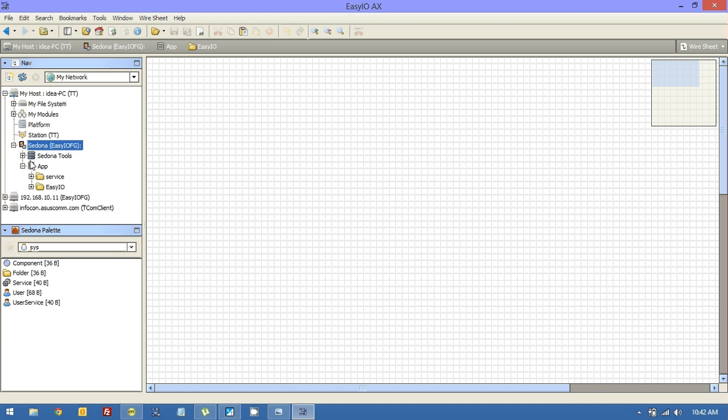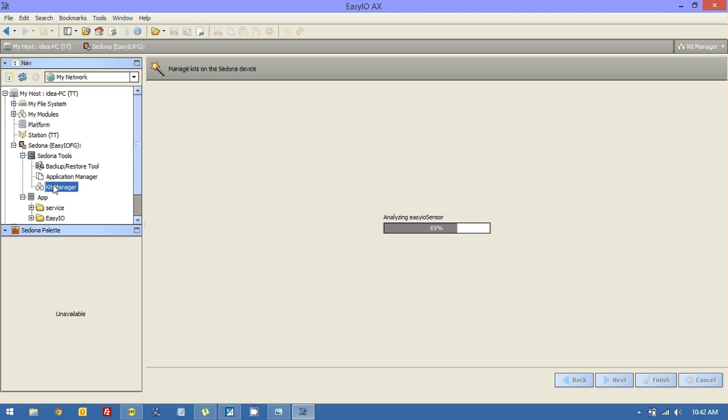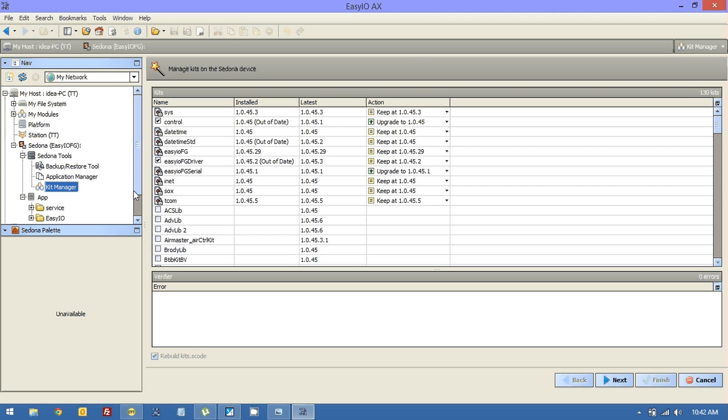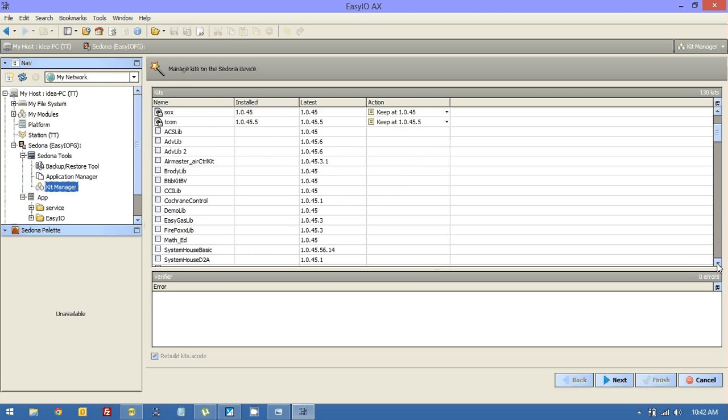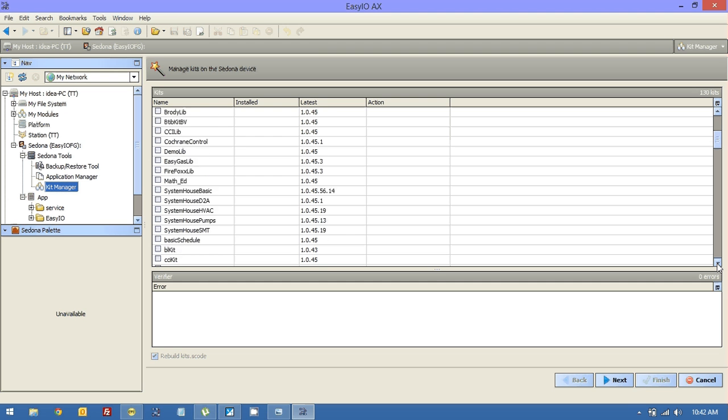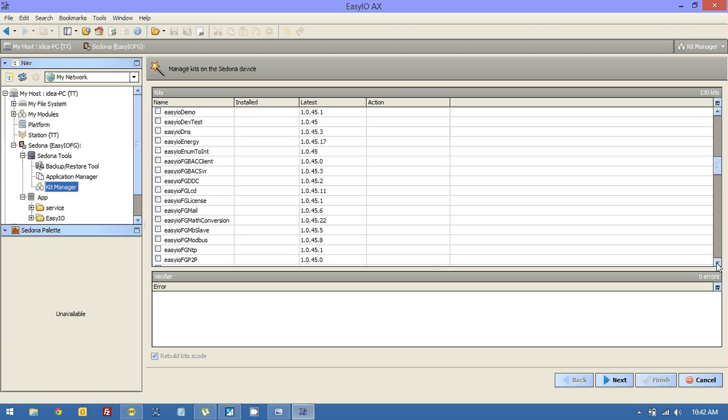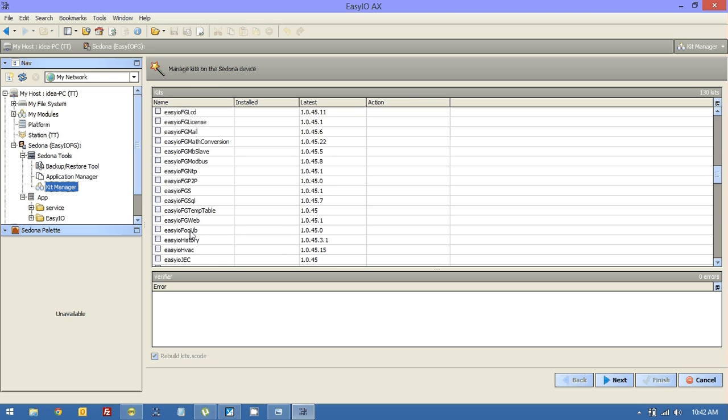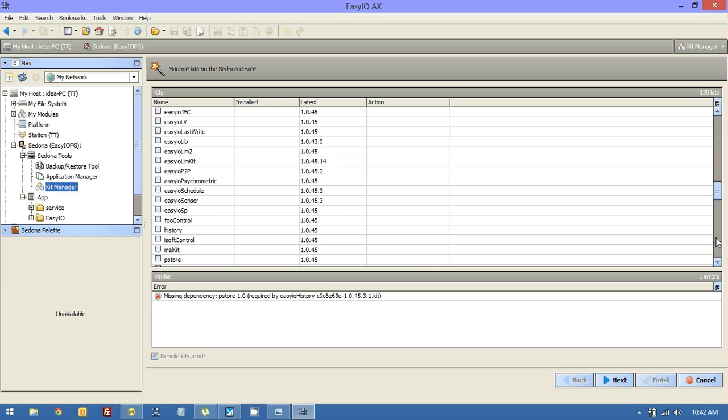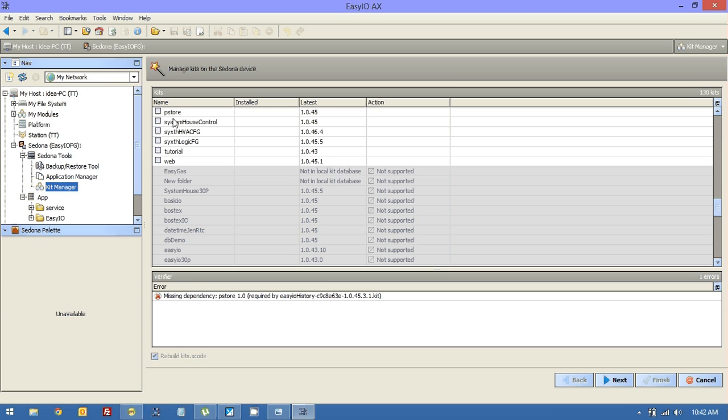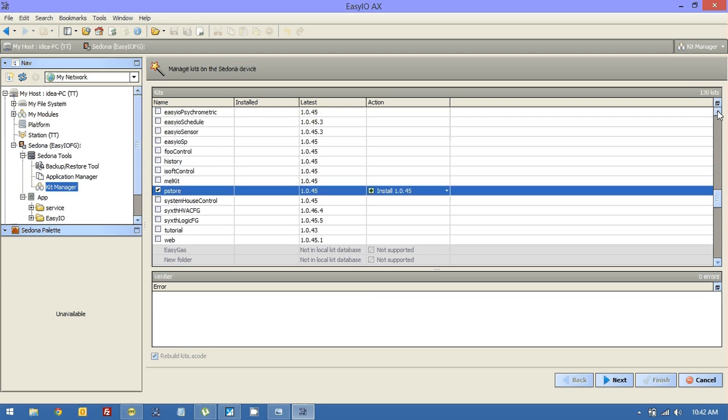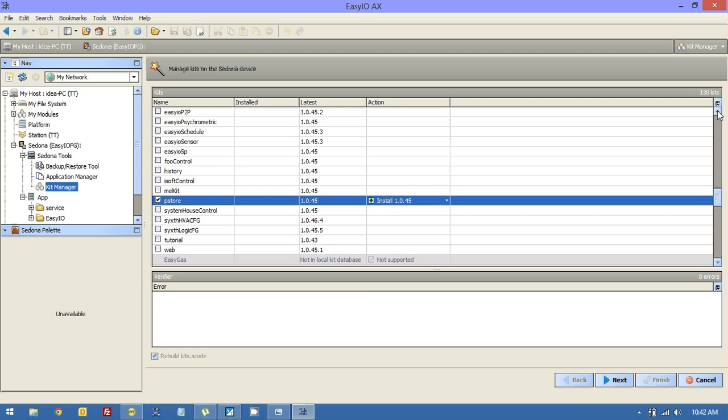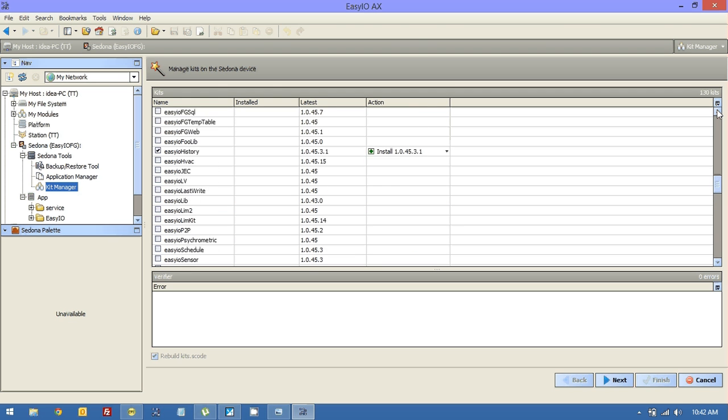Let's now go and add some more kits that I'm going to need. This time we're using Workbench. All I'm going to add in now is the EasyIO schedule and histories. Just looking for those here. I don't see them just yet. There's the history. That's telling me I need pstore, which I know. pstore stands for persistent storage. That allows us to save up to 4,000 records.